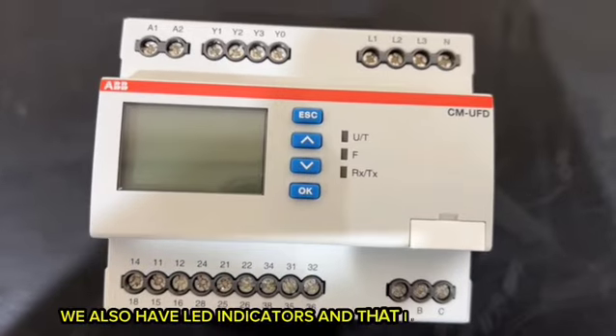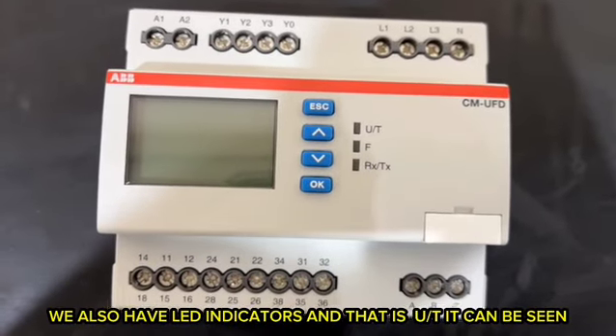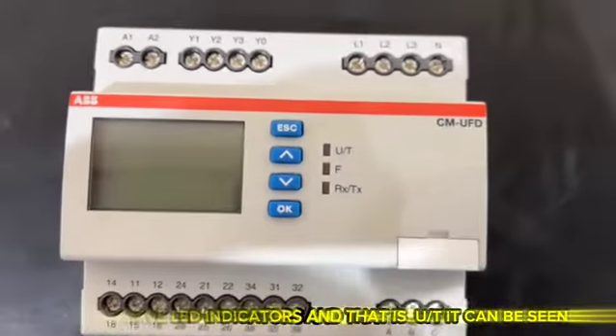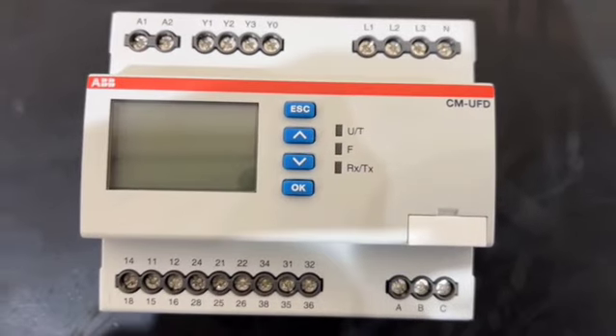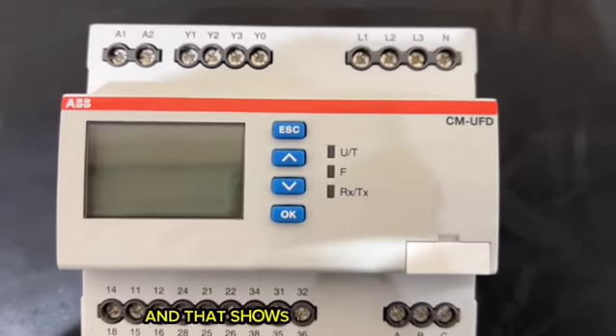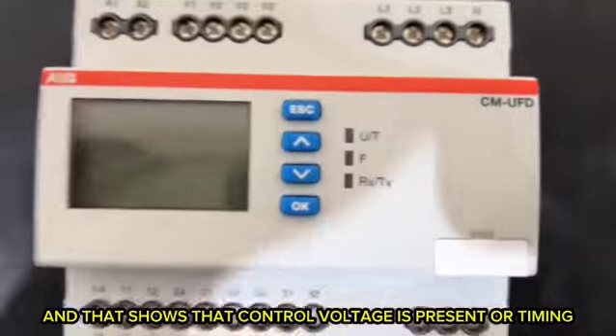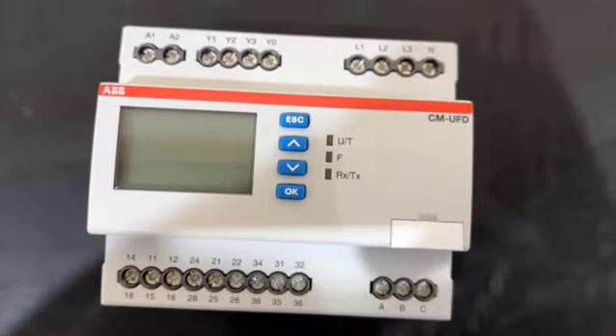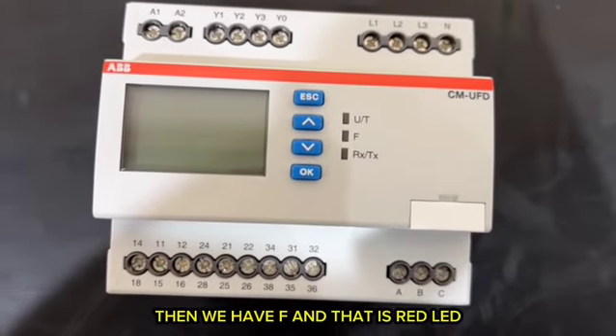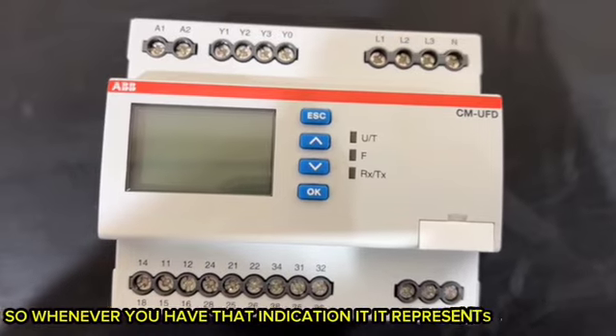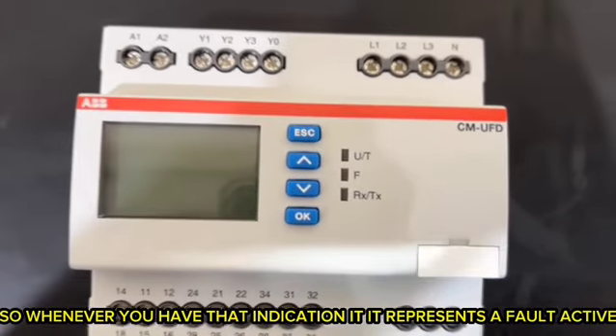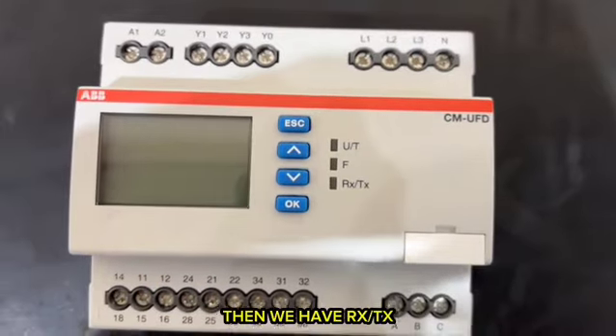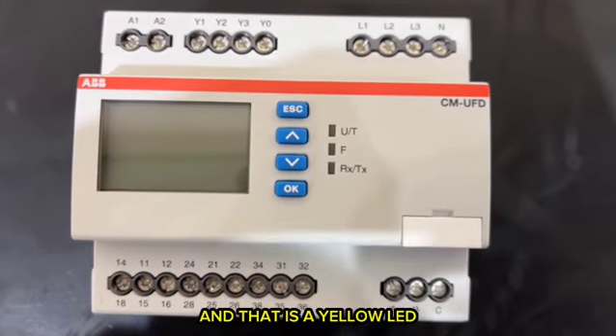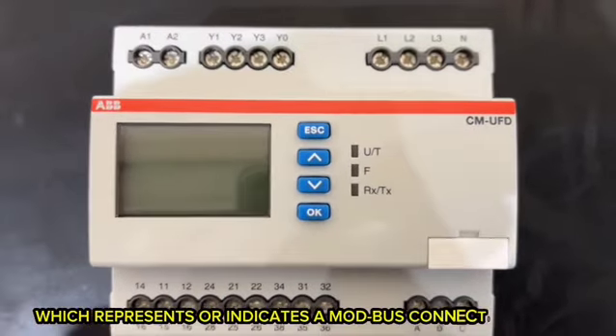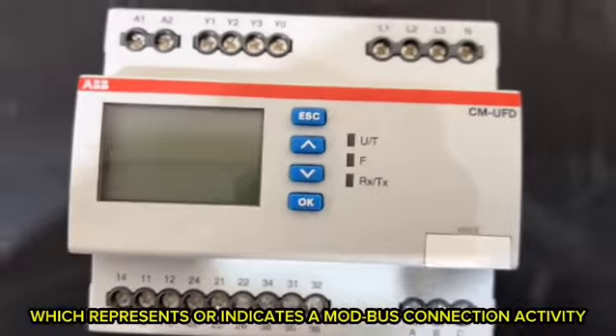We also have LED indicators, and that is U/T. You can see it. That is a green LED, and that shows that control voltage is present or timing is in progress. Then we have F, and that is a red LED. Whenever you have that indication, it represents a fault active. Then we have RX/TX, and that is a yellow LED, which indicates Modbus connection activity.